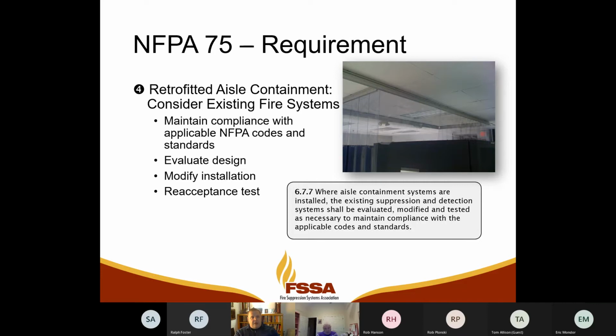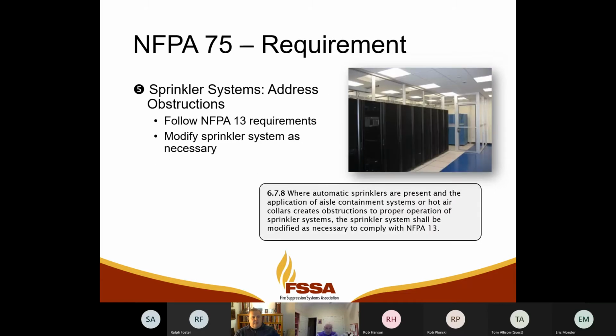You've got to maintain compliance with the applicable codes. So that's mostly we're talking about NFPA 13 for sprinkler systems and sprinkler spacing, obstructions, and NFPA 2001 for clean agent systems, obstructions. And of course, as you asked, Steve, if there was a water mist system, you need to address that too. Evaluate the design, modify the installation as necessary, and then have a re-acceptance test of the installation. That's what the code says to do.